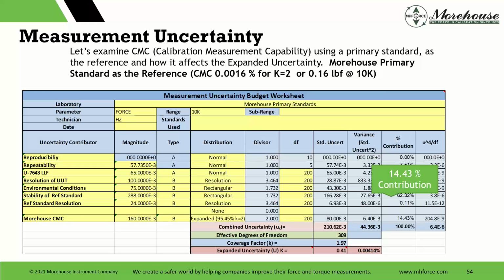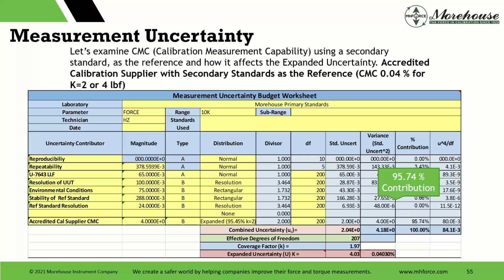So if we use the primary reference standard, same, a little bit different budget here. We switched to a 10K with a primary standard calibrated in dead weight. This is 0.004%. The reference standard is 14.43% of our overall contribution to uncertainty. This is dead weights. Now we switch to secondary standards.